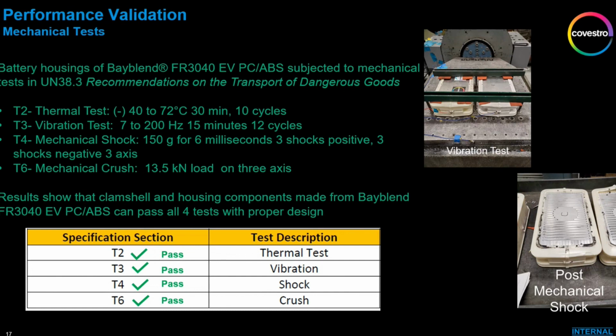So let's talk about some of the tests that were done. We wanted to prove out that the materials, especially in this case the housing, which is going to see the brunt of any type of mechanical loading, could be made from Bayblend FR3040 EV and meet expected performance requirements. We chose to look at a test that is probably the most universal test you can look for in batteries. It's the UN 38.3 Transportation of Dangerous Goods standard. So any battery or pack that's shipped anywhere in the world needs to meet that requirement. And within that requirement, there are 4 mechanical tests that we chose to look at to compare our materials. That would be the thermal test, a vibration test, mechanical shock, and then the mechanical crush test.